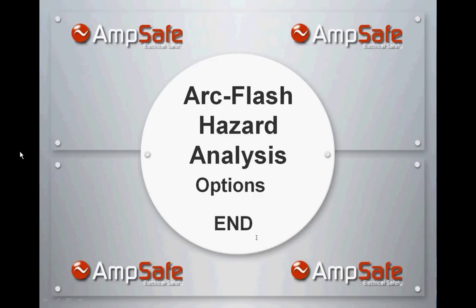Do you come across many scenarios where the software doesn't correctly calculate ArcFlash incident energies? Not me. I have not come across scenarios where the software does not calculate the right incident energy. How do I know that without actually doing a calculation by hand? Because that would be the way to double check the ArcFlash incident calculations that the software gives you: calculating it by hand and comparing them.